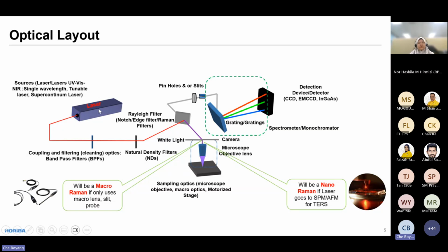When the light comes out from the laser, it will go through some filters. It will go through the so-called bandpass filter, which reduces the light source at other wavelengths. It narrows down your incident wavelengths, so you get a pure signal from your laser and remove the noise. After the bandpass filter, it will go through the so-called neutral density filter, or ND filter. It helps you reduce the power of your laser. It could be either 100% or 10% or 1% of your original full-power laser. This is helpful when you are dealing with very fragile samples, and if you do not want to burn out your sample, you can use the neutral density filter to reduce the power of your laser.